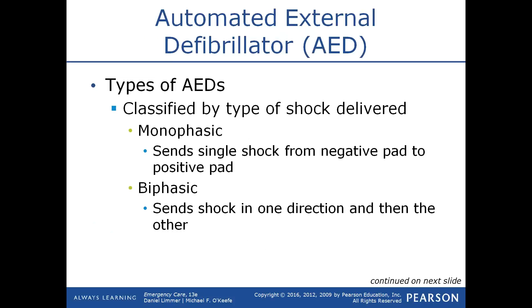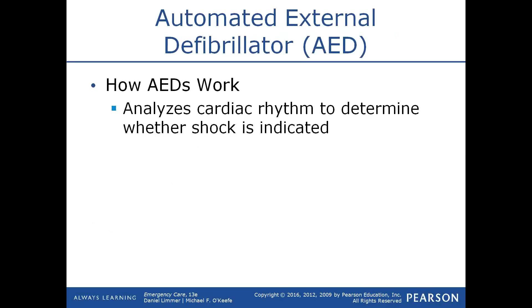What we use now is called biphasic energy. And biphasic AEDs send a shock in one direction to one pad and then turn around and send it back through the other pad. So the heart gets exposed to electricity twice instead of once. The nice thing about biphasic AEDs is that because of that less energy, less damage is actually done to the heart when you defibrillate it. Now, AEDs work because they analyze your rhythm to determine whether or not it is shockable. And if it isn't shockable, it'll tell you no shock advised.